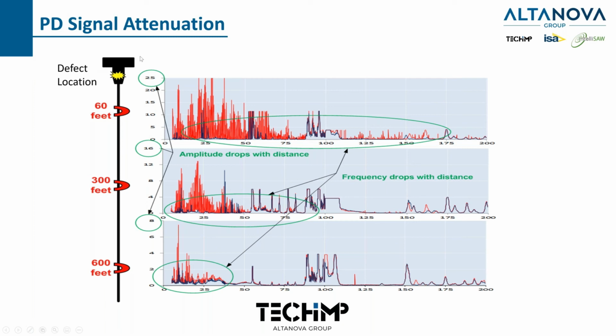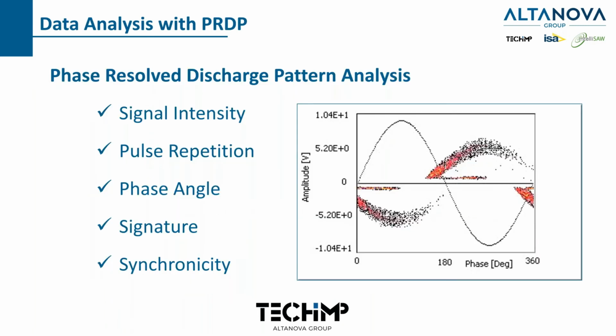So the next step after location is to identify the asset, or identify the type of discharge. So that's where the phase resolved discharge pattern comes in. Remember when we started, we saw those graphs and the dots like this, and this is what's going to tell us what types of PD, partial discharge, we have.